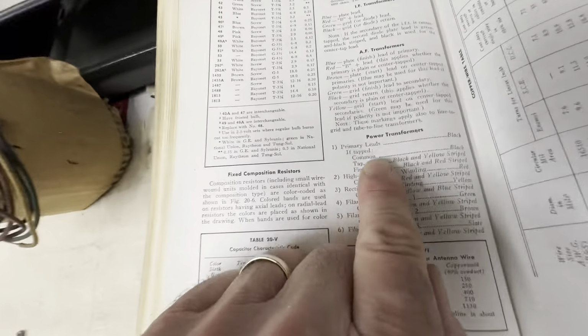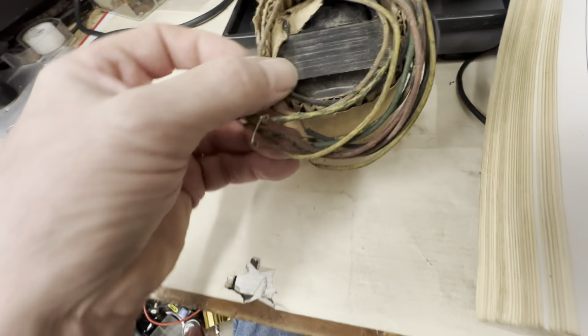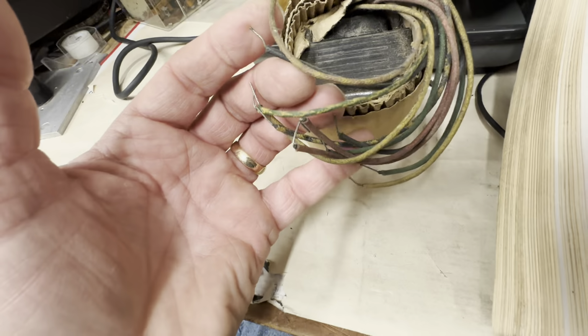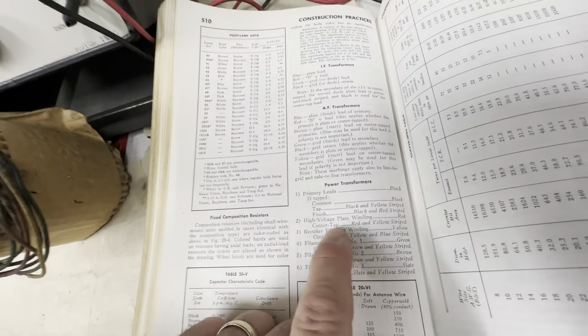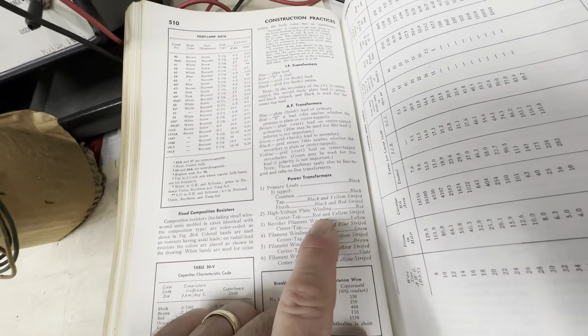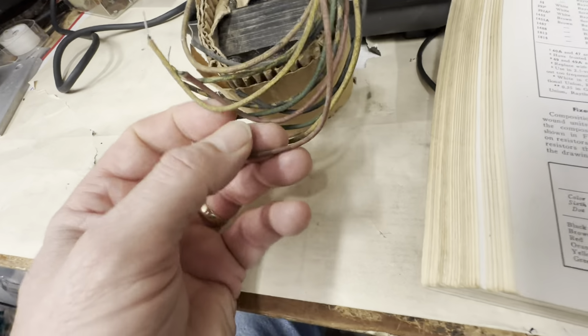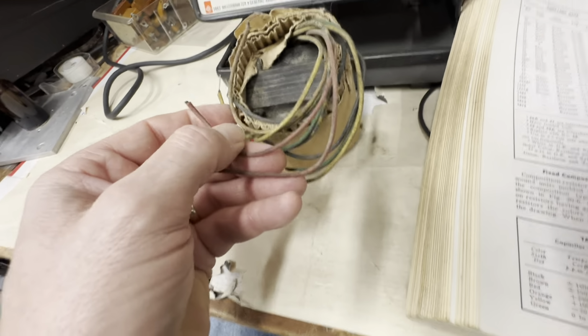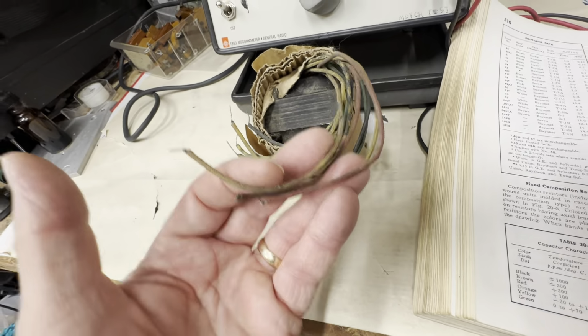Okay, so the primary leads on this transformer are black. So you've got the black here and a black down there. So that's primary. That's going to probably be 110. High voltage plate winding is red, and the center tap is red yellow. There's our reds, and there's a red yellow right there. So we know that that's our high voltage winding.